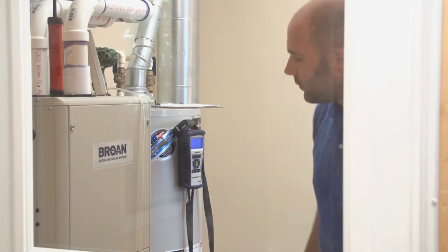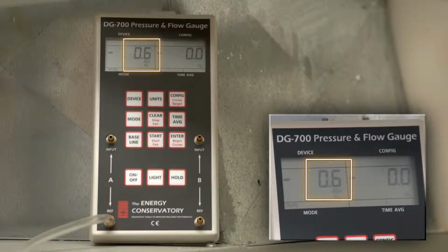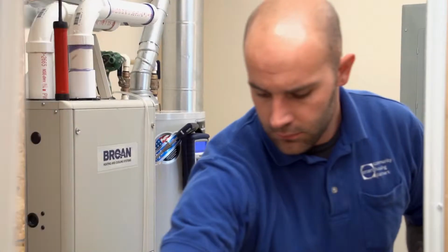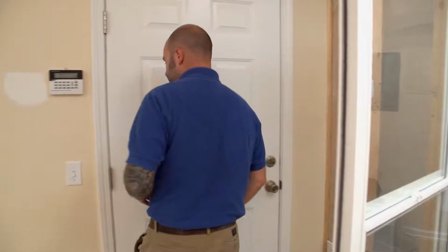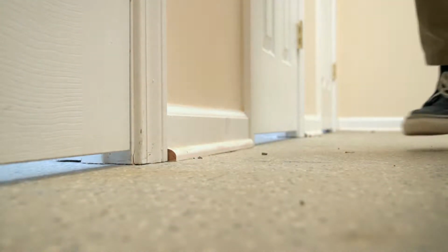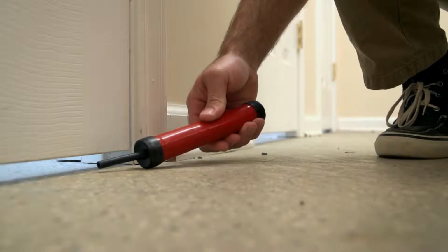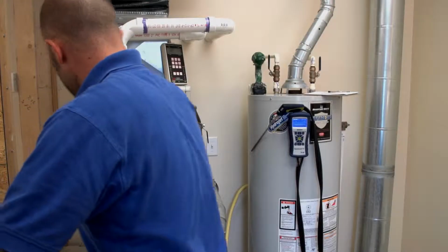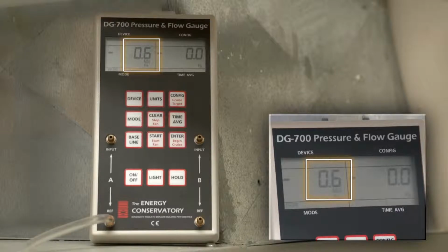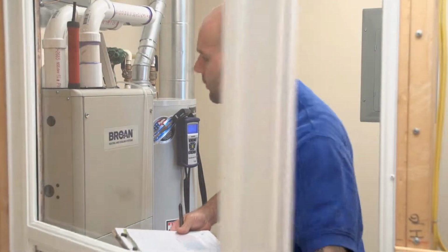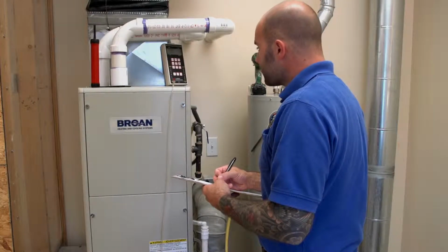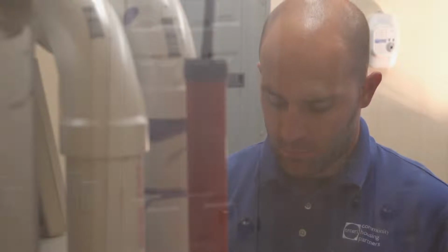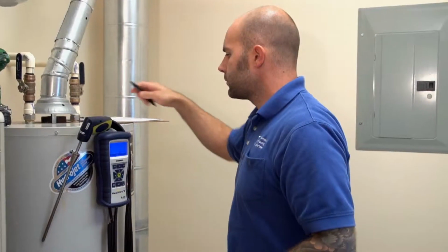Close door between CAS and main body of the house and record the pressure. Next, open door between CAS and the main body of the house and record the pressure. Then, turn on the home's air handler. Start at the farthest door from the CAS and smoke all doors returning to the CAS. If the smoke hits your nose, leave the door closed. When you get back to the CAS, close the CAS door and record the pressure. Now open the CAS door with the air handler running. Record the pressure. Choose a scenario which resulted in the most negative pressure in the CAS. Record the worst case depressurization from channel A on the DG700.